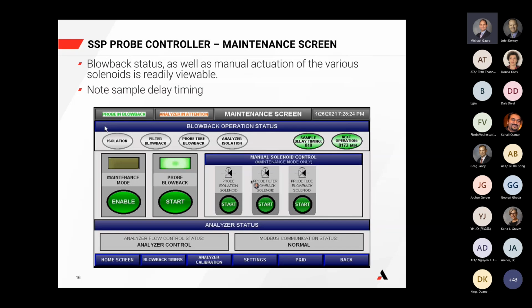From this screen, you can also test your various valves. You can click on here and actuate the solenoids and make sure that they're working. And you'll see throughout the screens that we like to repeat the status of the various components of the SSP, and that extends down to the analyzer controller. Here we also have an indicator that everything's going well with our Modbus communication. So again, this looks like everything's operating as it should. And again, this is the maintenance screen. If we go to the next one, that'll be our analyzer calibration screen.